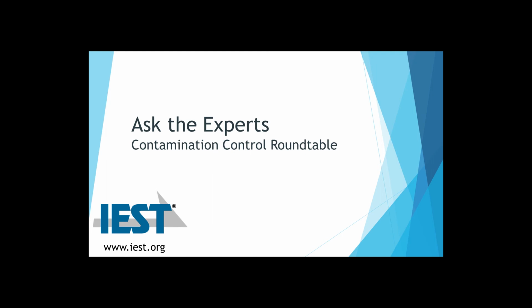One quick comment, though. I hope everybody on the line, whatever you do, do not certify a room with 1 sample. Take the advice of people who have been there and have waited a very long time for the particle count to achieve the minimum number. In some cases, if the room is very clean, it could be days. So please always take 2, even though the standard allows you 1. Go ahead and take 2.